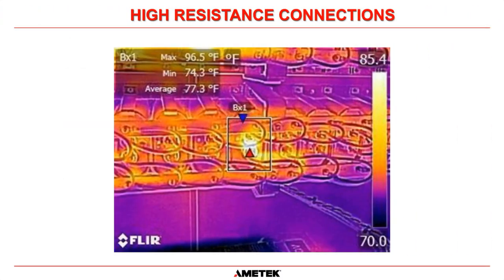And here's a great example of, during a planned maintenance visit, one of our field service engineers found a high resistance connection. And it's very difficult to tell for most people from here, but these are capacitors, AC capacitors within our UPS system. And there is a terminal here, and there is a terminal here, there's a terminal here, and a terminal here. Okay, you can see on most of the capacitors, the terminals are not showing up as a hotspot. But on this terminal here, it is showing up 20 degrees Fahrenheit above every other connection. So that was brought to the FSE's attention when he took this picture.